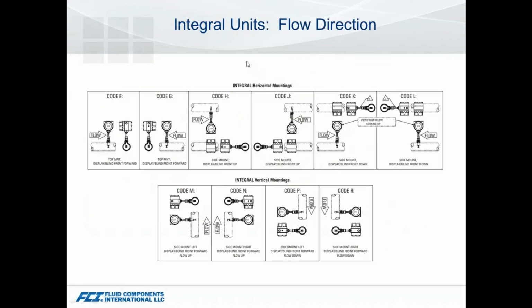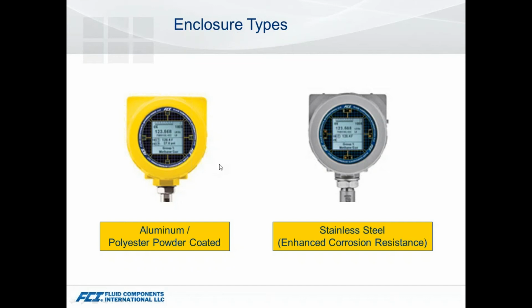With the integral units on the 50 and 75s, we really need to pay attention to this direction chart that we provided so we make sure it's oriented properly: top, side, vertical up, horizontal left to right, things of that nature. You have to keep in mind that if you order a unit with a display, how is the customer going to be looking at it in the field? If we've got that orientation incorrect, it's not something that can easily be corrected in the field. Standard enclosure types available are aluminum and polyester coated. We actually have stainless steel enclosure options on all of our flow meters, the Economical as well as the higher end.